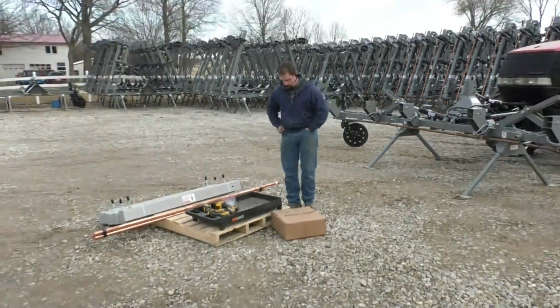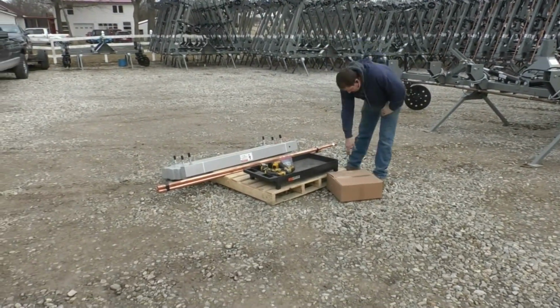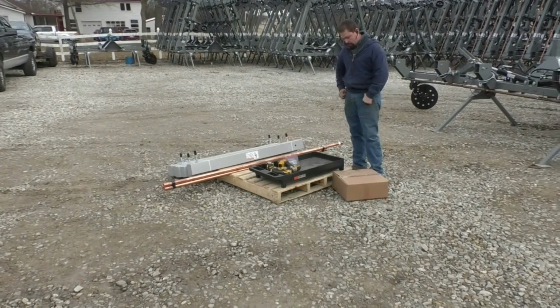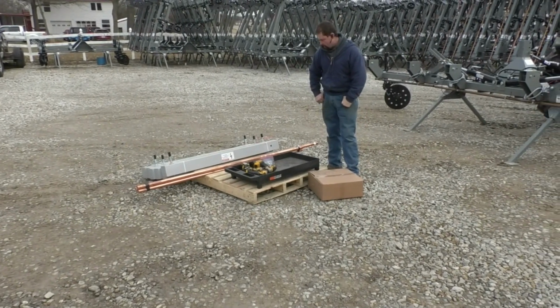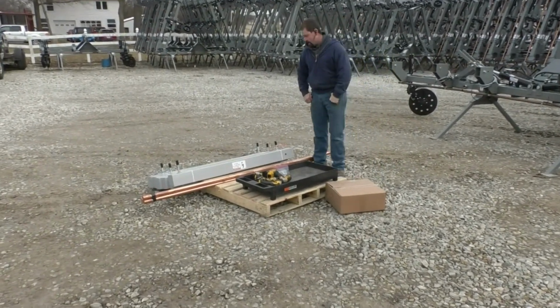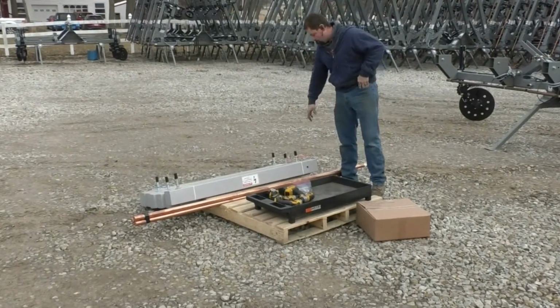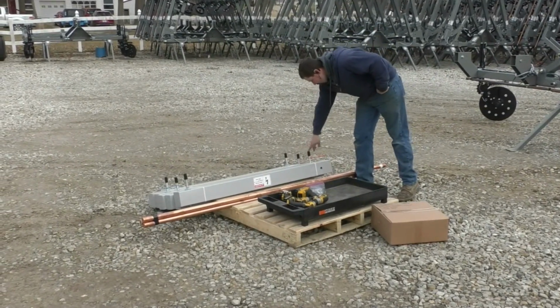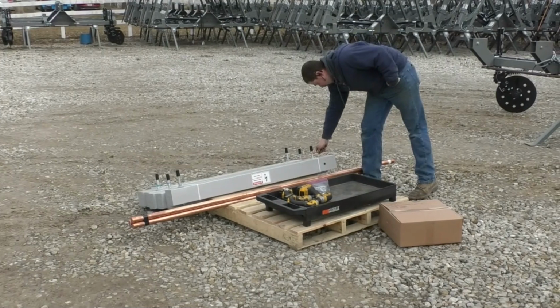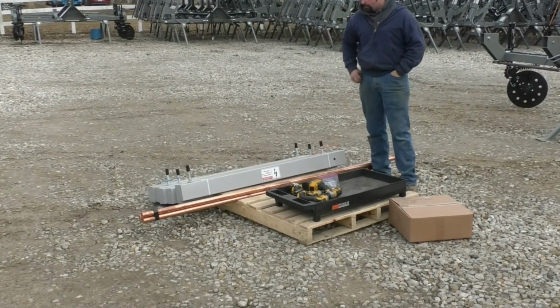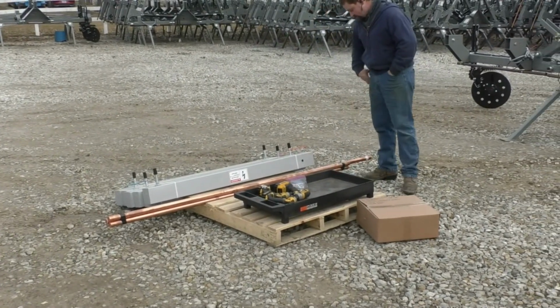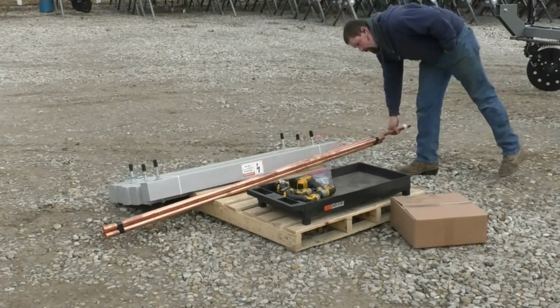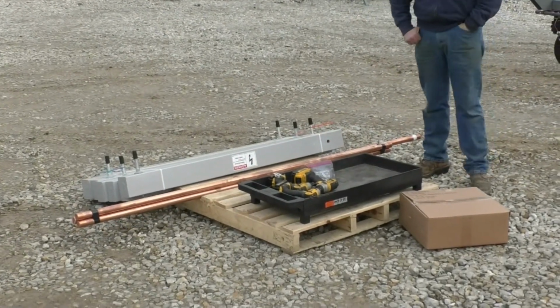So at this point, we're going to go ahead and do final assembly on it. Shipped along with the unit was a box like this one. It has 6 insulators, 4 shims, some wing wire brackets, some other parts to it. You have a group of insulator arms that were shipped along with the unit. They will have the stems in them. Notice the colored zip ties on the stems. Those are important. You will also have a group of high voltage copper that is used on the machine itself.